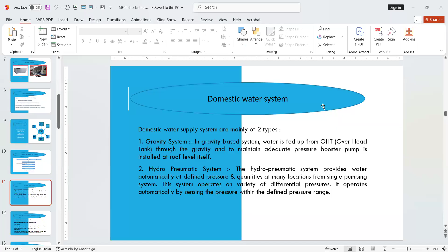As soon as someone opens any tap in their bathroom or wherever, what will happen? The pressure will automatically reduce. When the pressure reduces, the pump will restart to maintain the pressure in that particular line from the pump till the flat. Now, hydropneumatic water systems are of two types. First one is tap feeding, another one is tank feeding.